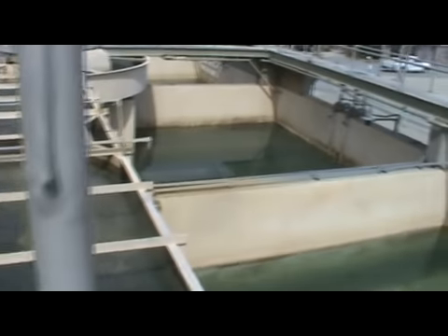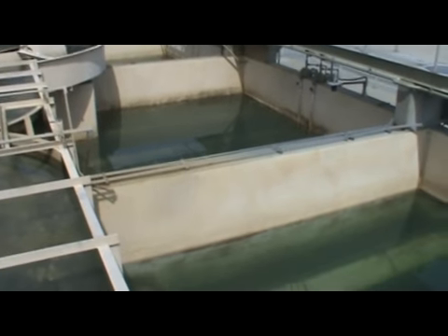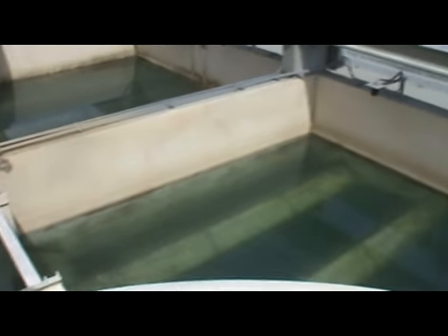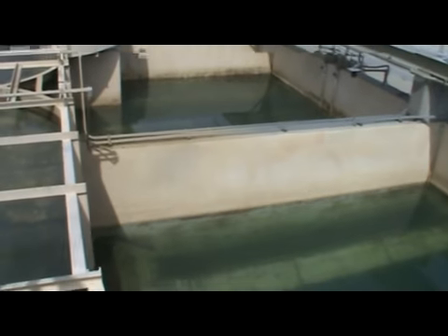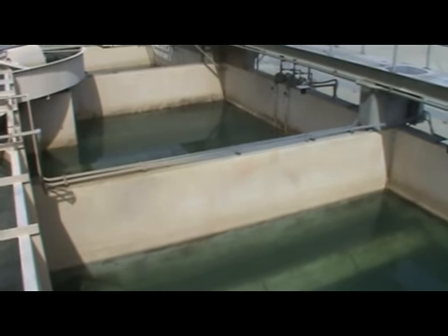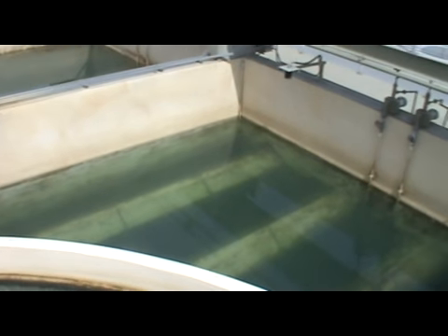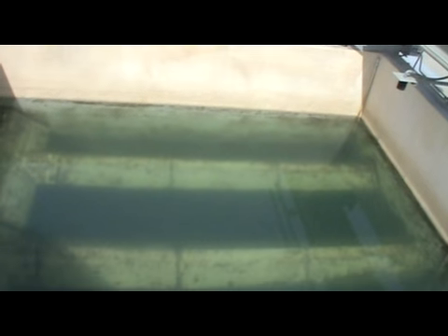There are generally 3 things that we use to determine when it's time to backwash a filter. Time: the time that filter's been running, or you could think of that as the gallons that filter has produced. Turbidity: if the effluent turbidity starts to rise a little bit on that filter. Or head loss. When I talk about head loss, I mean the filtrate, the water coming out of the other side, starts to slow down. It's not as great.